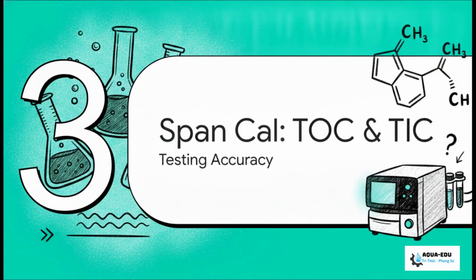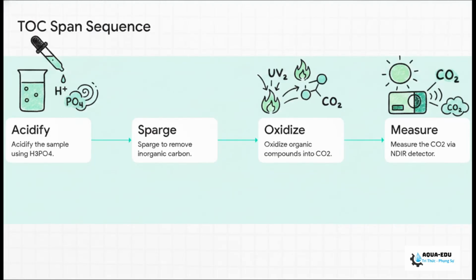All right, Section 3, Span Calibration for TOC and TIC. With a rock-solid 0 recorded, we now test the analyzer's accuracy using our 500 ppb carbon sucrose, or KHP standard. It is super vital to understand what the machine is actually doing during this automated 6 to 10 minute cycle.